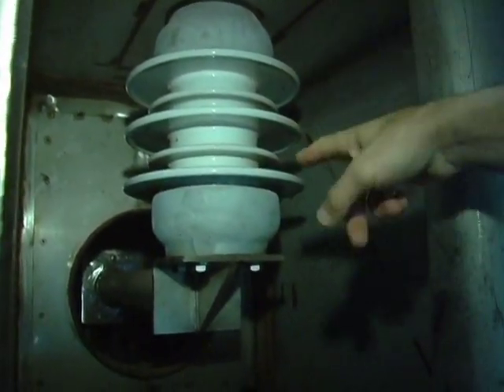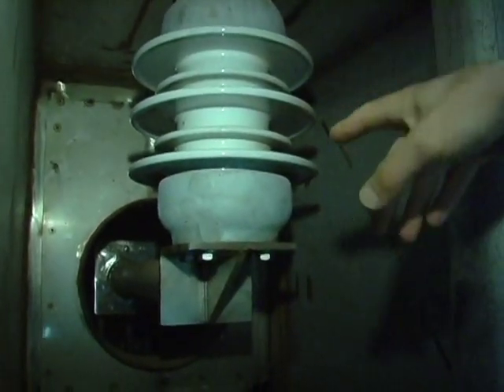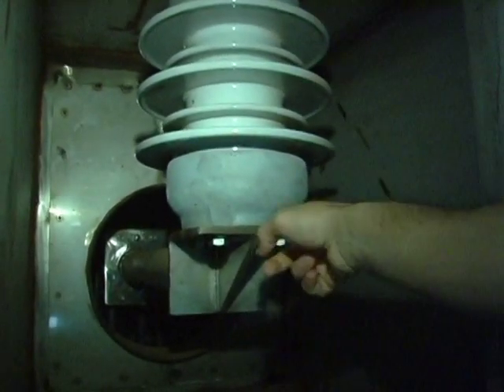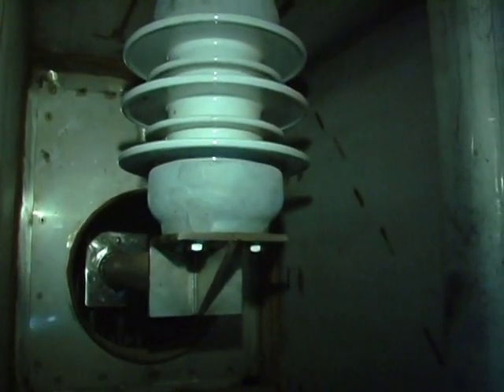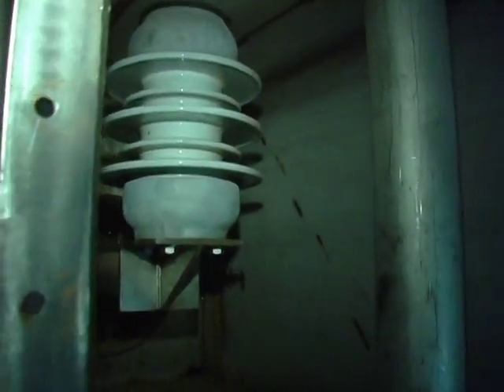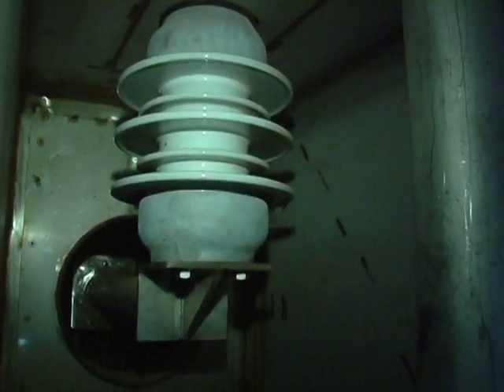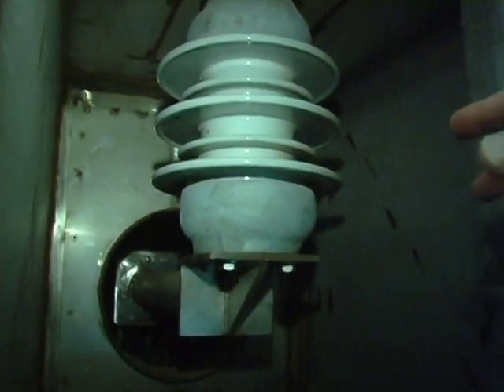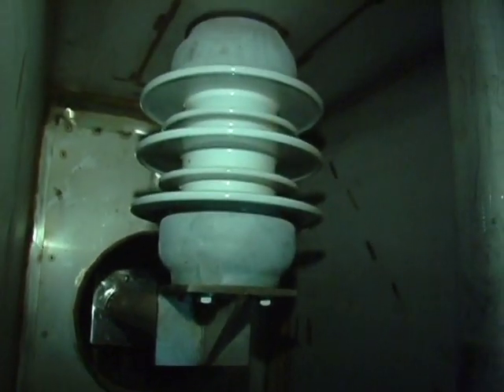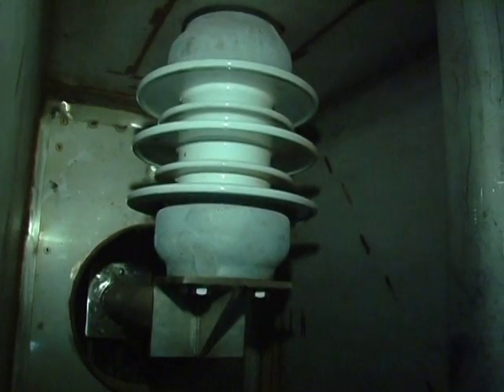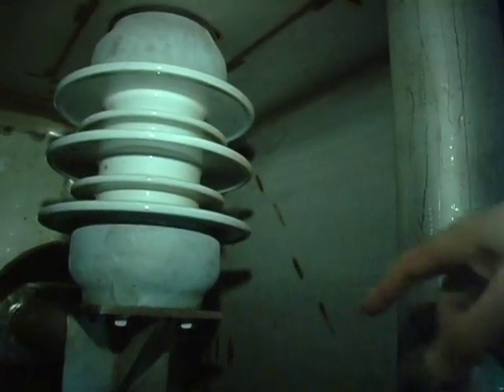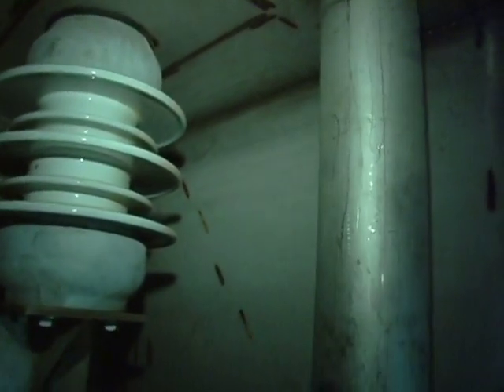Now you don't want to get this thing dirty either. You got to keep these things clean, or else you'll arc current right across the insulator. Oh wow! I didn't know that. Yeah. Once it's all bolted up, it still can get dirty from backsplashing water, or the flue gas itself can have dirt in it. So we have this purge air system that supplies air in there. Oh, it's hollow, yeah. Air can come out of here. See, we're blowing air through. And we've got a slide gate to adjust the airflow too. Oh, okay.